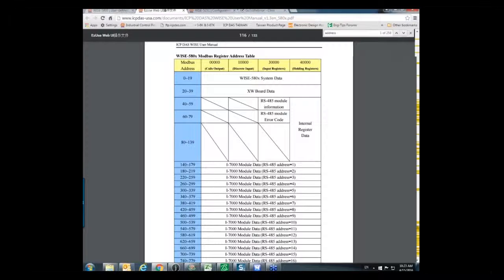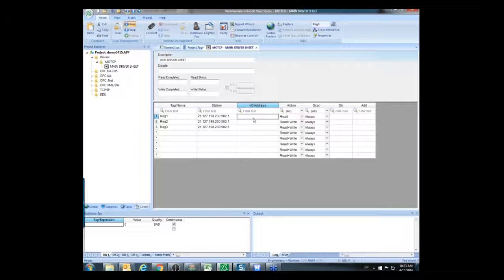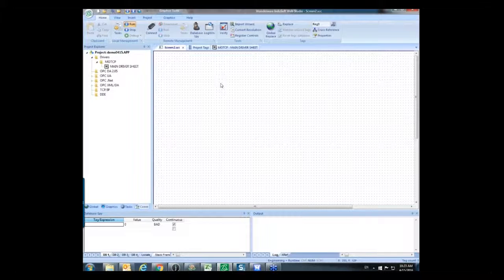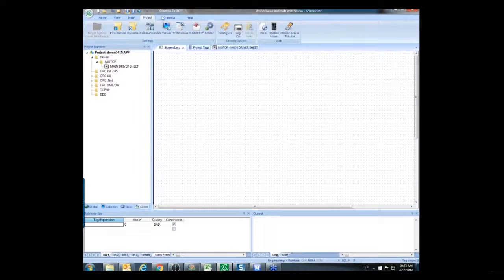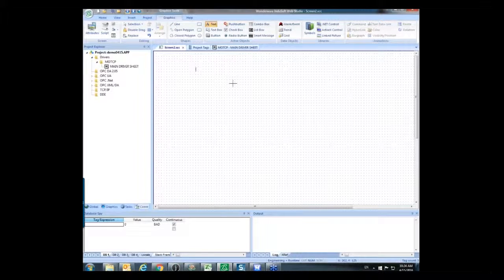And the station will be the IP address for the WISE 5800 module, which is 21.127.198.230. The port is 502, address is 1. All should be the same. And for the I/O address, you can look at the Modbus register address table from the user manual. This is the user manual for the WISE module. You can see that 0 to 19 is the system data, 20 to 39 is the XW port, which is the expansion port data, etc. You can also pull the data from the i7000 modules.